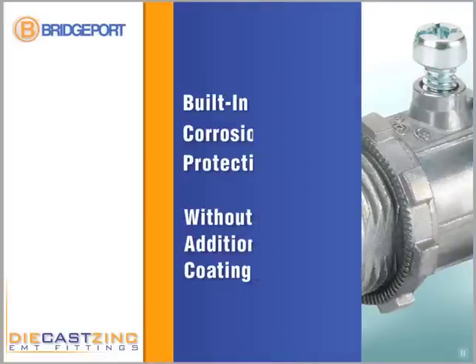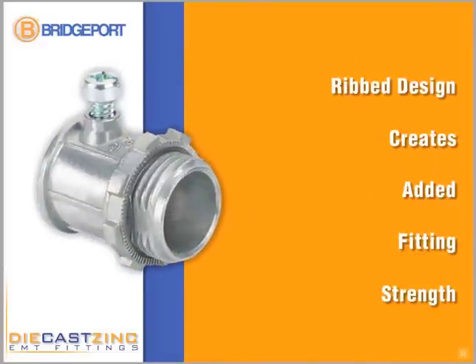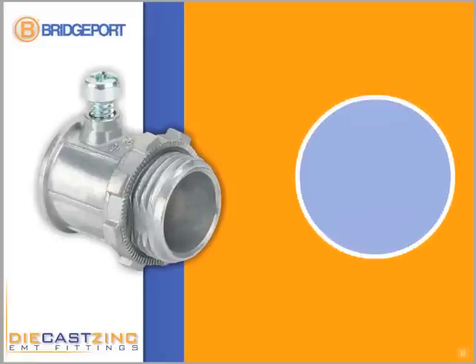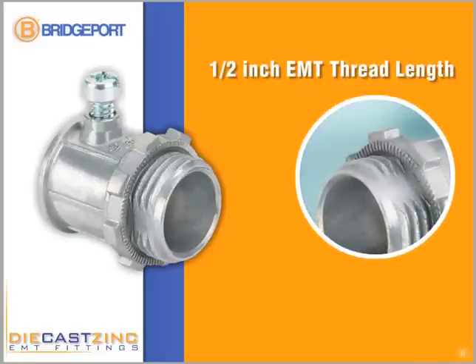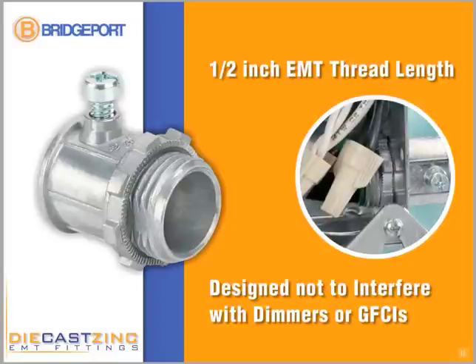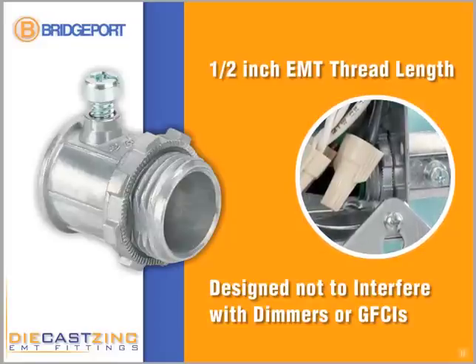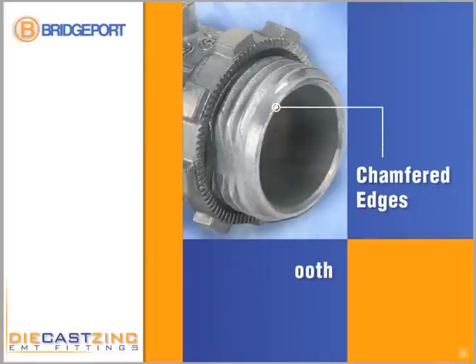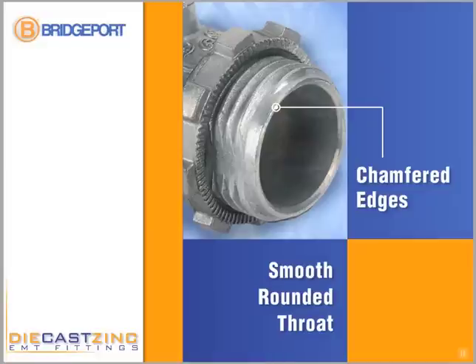additional coating. A rib design creates added fitting strength, and the smooth bore speeds conduit installation into the fitting. Bridgeport's half-inch EMT connector thread length is designed not to interfere with devices such as large dimmers or GFCIs that might require more space. Chamfered edges and a smooth rounded throat prevent conductor damage as the wires exit the fitting.